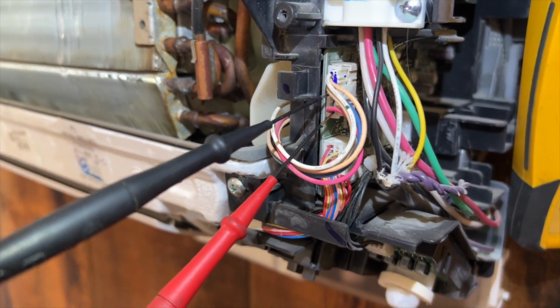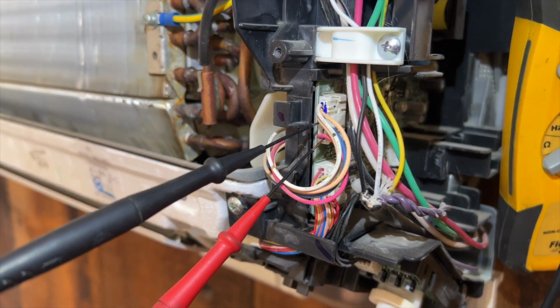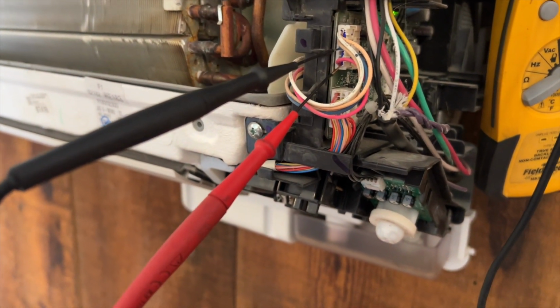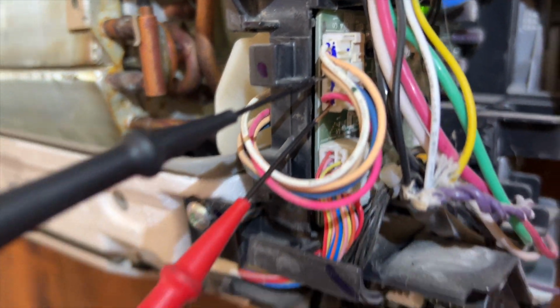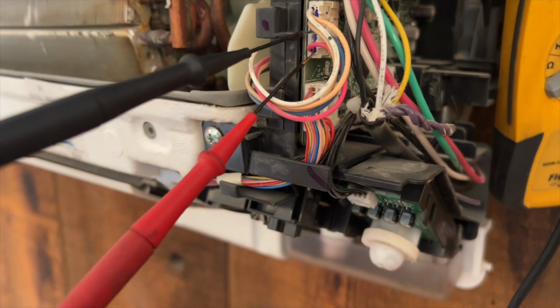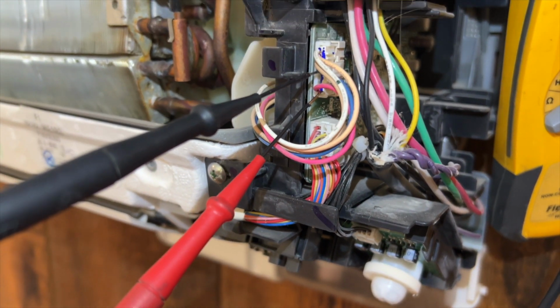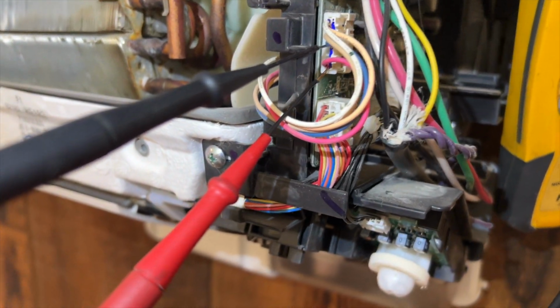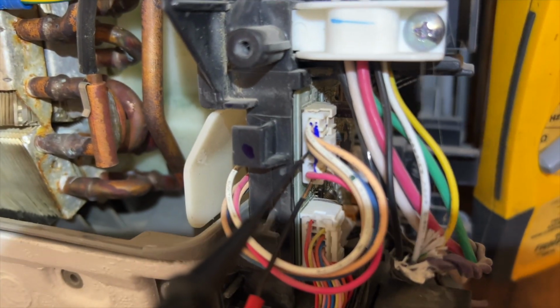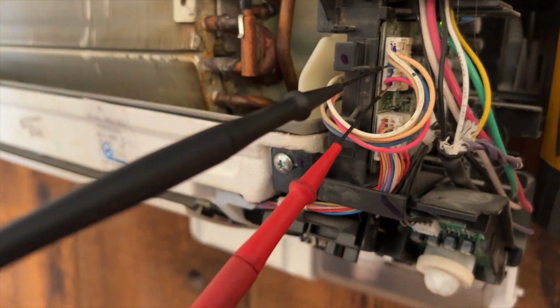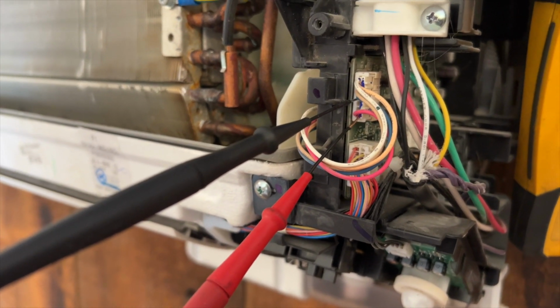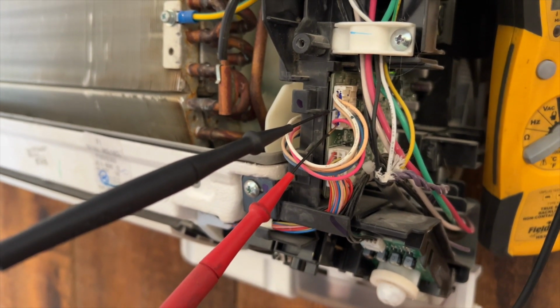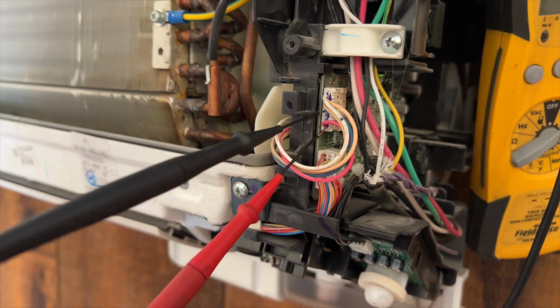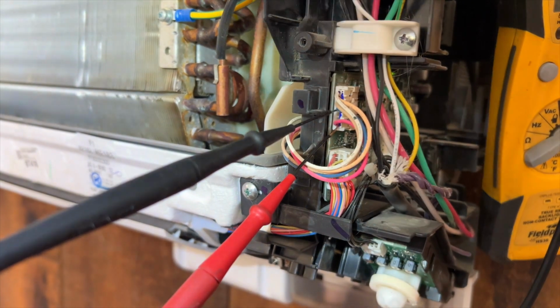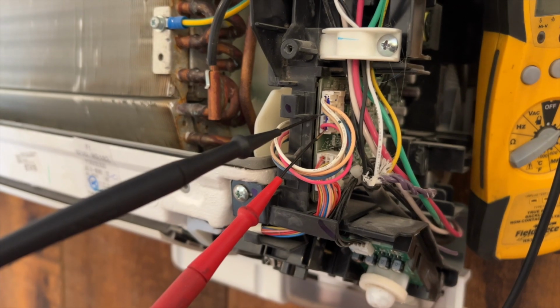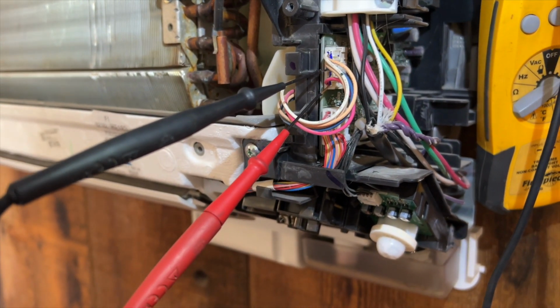All right, so we're checking the motor voltage just to make sure that the board is functional. So we have 7 pins right here. The one on the very bottom is going to be pin 7, and the one on the very top is pin 1. Pin 4, which is that blue wire right there where my black lead is, that's our common, or a ground. So we're going to be checking our motor power supply voltage. That's going to be volts DC, and it's going to be 310 to 340 volts DC.